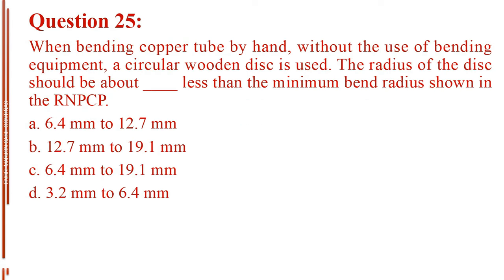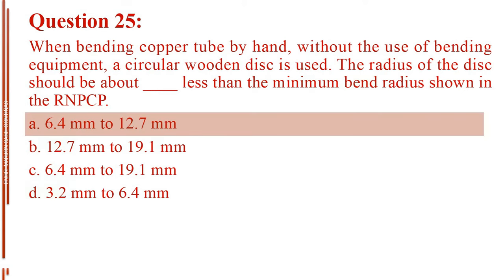Question number 25. When bending copper tube by hand, without the use of bending equipment, a circular wooden disk is used. The radius of the disk should be about blank less than the minimum bend radius shown in the RNPCP. Letter A, 6.4 mm to 12.7 mm. Letter B, 12.7 mm to 19.1 mm. Letter C, 6.4 mm to 19.1 mm. Letter D, 3.2 mm to 6.4 mm. The answer is Letter A, 6.4 mm to 12.7 mm.